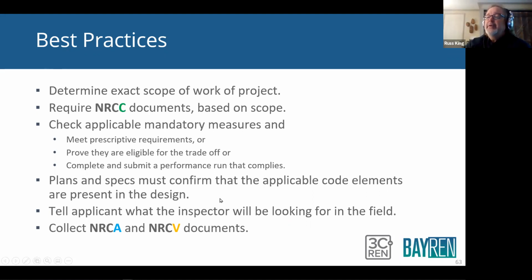Plans and specs must confirm that the applicable code elements are present in the design. For example, if it says you have to have individual switching in these new offices that you're creating, make sure the lighting plan shows that. Make sure that information is incorporated into the plans, because that's where the trades are going to look. They're going to look at the plans, so it's good to make sure that the plans match the requirements.